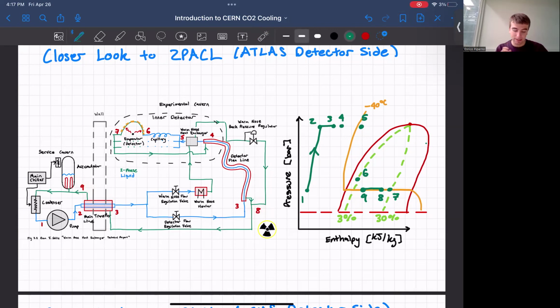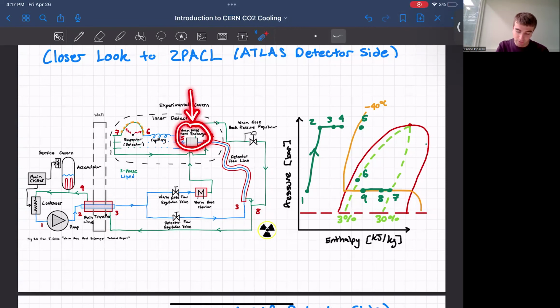The detector flex line will have the same exact purpose as the main transfer line. Thus, point 3 will be shifted to the right to point 4, and point 7 to the left to point 8. The warm nose heat exchanger will cause a further increase in enthalpy to the refrigerant. The warm CO2 is split from the main transfer line and is heating up this incoming CO2 here. Then the capillary will cause a decrease in pressure from point 5 to 6. From point 6 to 7, we enter inside the evaporator where the refrigerant is boiling, or in 2 phase. Then, skipping back to point 9, the fluid is condensed by the main chiller and shifted to the left back to our starting point.